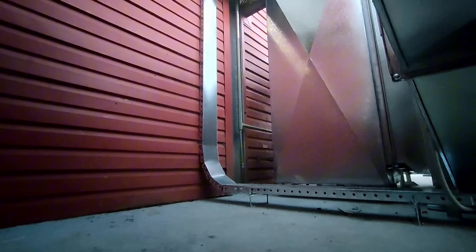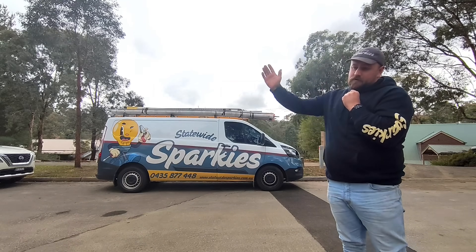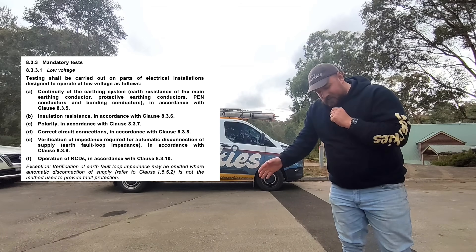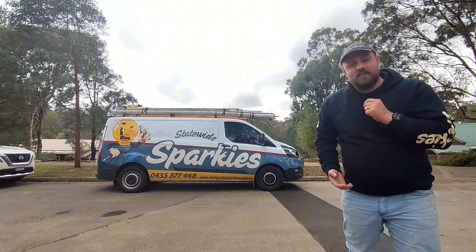So we did the seven mandatory tests for this job. There actually was only six to be done because there's no RCDs on this job. So I'm going to put them on the screen here because I always seem to forget them. But we covered the six that I needed to do. Obviously the first one is visual inspection — I installed it, there's no need to do that, but we covered everything.